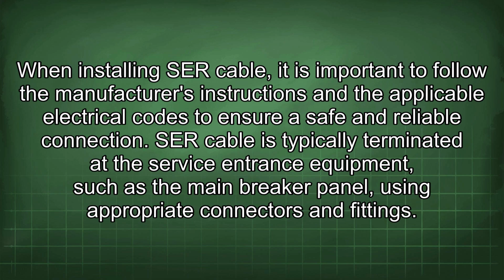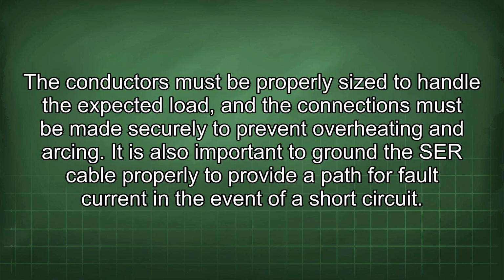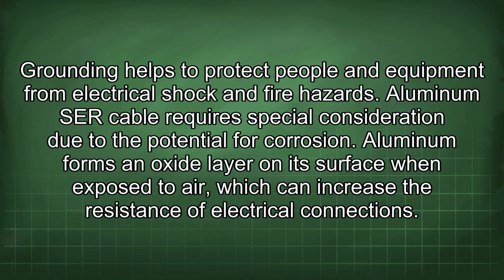SER cable is typically terminated at the service entrance equipment, such as the main breaker panel, using appropriate connectors and fittings. The conductors must be properly sized to handle the expected load, and the connections must be made securely to prevent overheating and arcing. It is also important to ground the SER cable properly to provide a path for fault current in the event of a short circuit. Grounding helps to protect people and equipment from electrical shock and fire hazards.